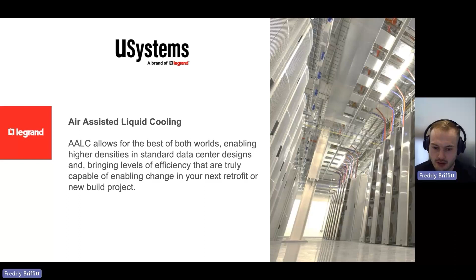I just wanted to talk about a real world example. Cambridge University's data center is 1.2 megawatts, and they have free cooling year round. They don't have any compressors on site. They've got a range of rack densities from low to high density, and the PUE on their cooling is phenomenal, 1.035.